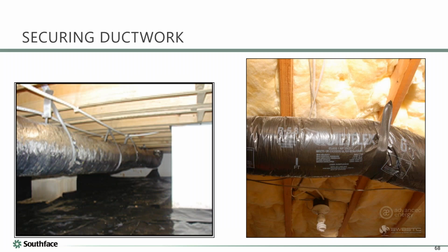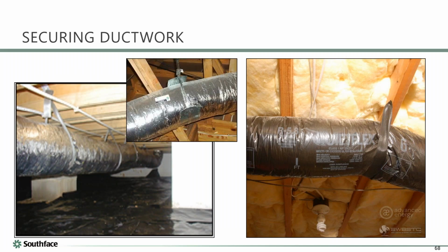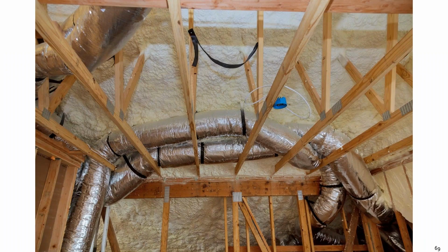And then put the register back on, and then seal the boot to the subfloor, or to the wall in this case. Supporting the ductwork with straps is important, as opposed to, I've seen some people hang it with like a coat hanger wire, and that's going to pinch the duct and the insulation.